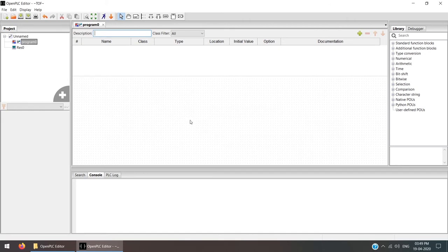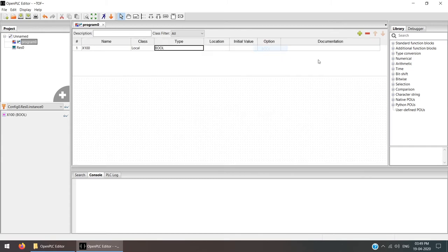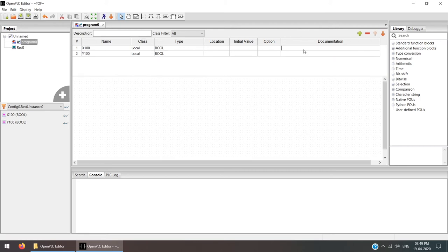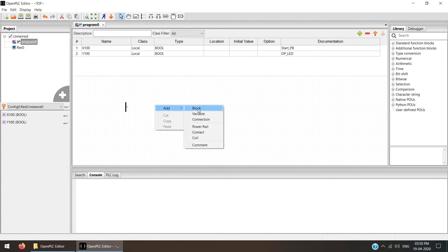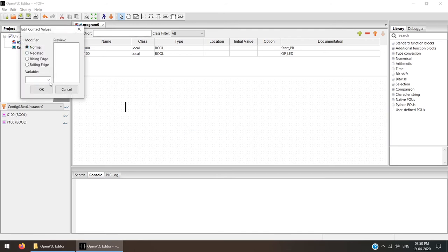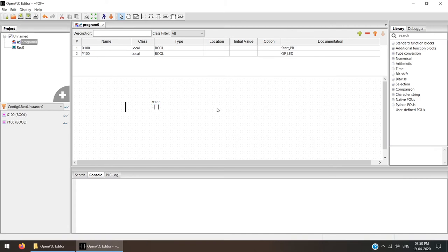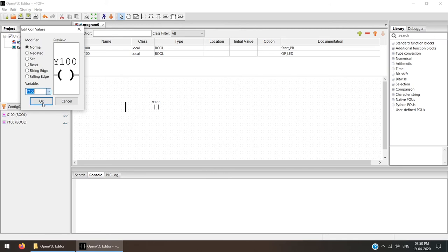Again, like the previous case, we keep the ladder coding simple with only two variables. First variable X100 — remember from the last video, change the base type to boolean. Second, output Y100 — by default it takes boolean. For documentation: X100 is 'Start Push Button' and Y100 is output LED. For the rung, right-click, add power rail (single), then add a normally open contact with variable X100. After that, add an output coil with variable Y100.